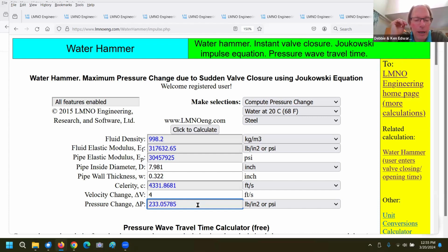So that's a lot thicker pipe wall or more serious material than you might think of if you're just designing for a steady state pressure of say 40. As your delta V increases, that number goes up even more. So if you're at 8 feet per second, then you've got 466 PSI surge pressure. And so this is your worst case. You are instantly dropping that velocity from 8 feet per second to 0 feet per second.